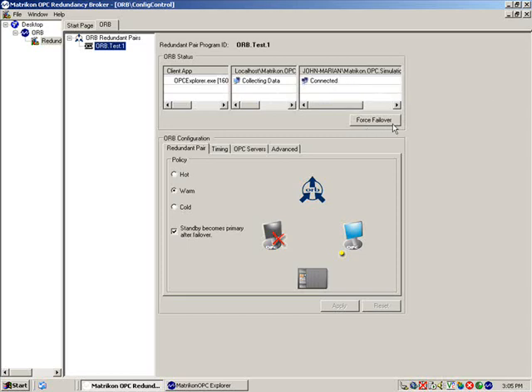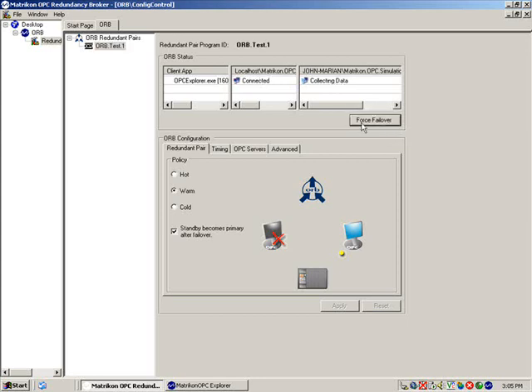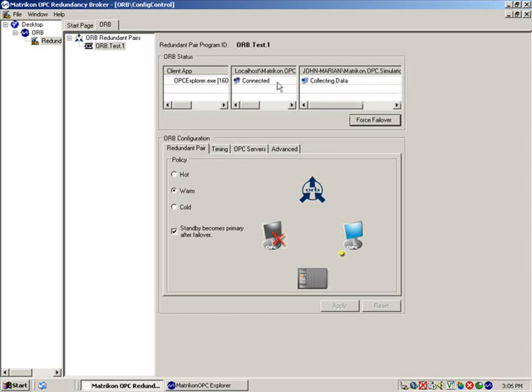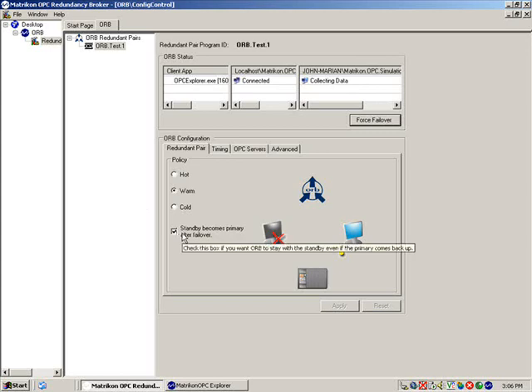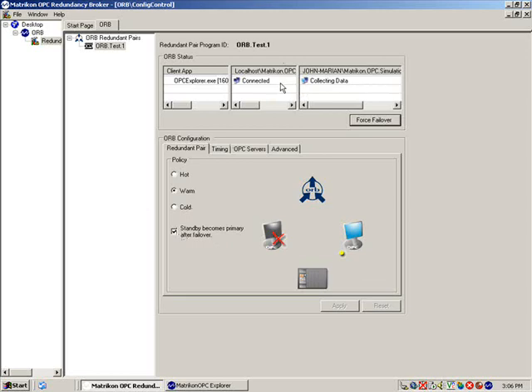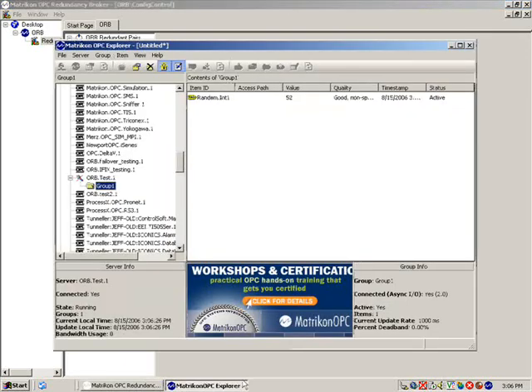We will use the force failover button to failover to the remote backup server. You will notice that the remote server is now collecting data while the local server is connected and waiting as a backup. That is because the standby becomes primary after failover option has been selected. If this option were not selected, ORB would fail back to the local server as the local server would be marked as the primary.